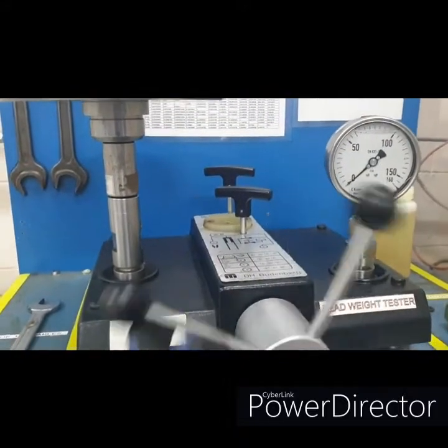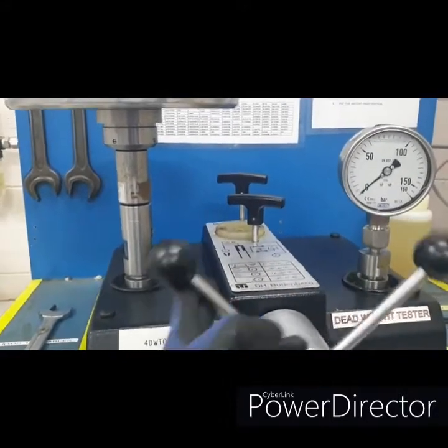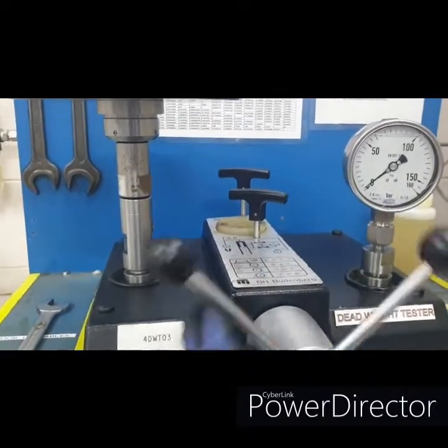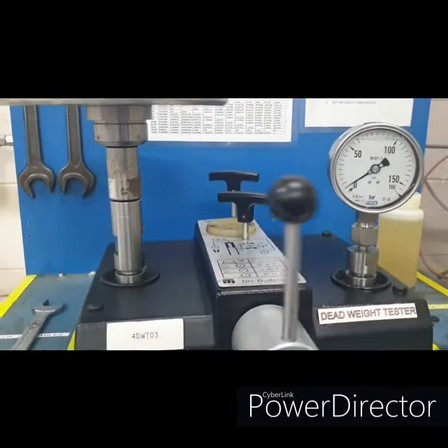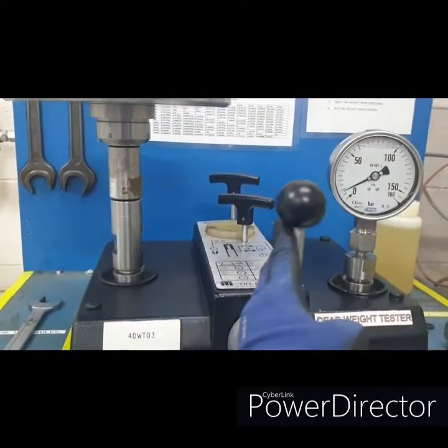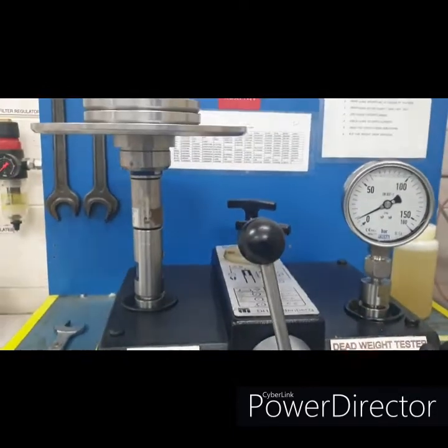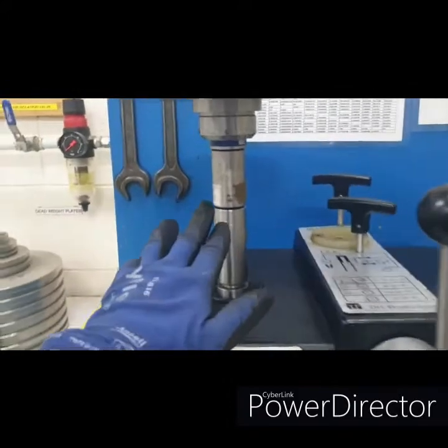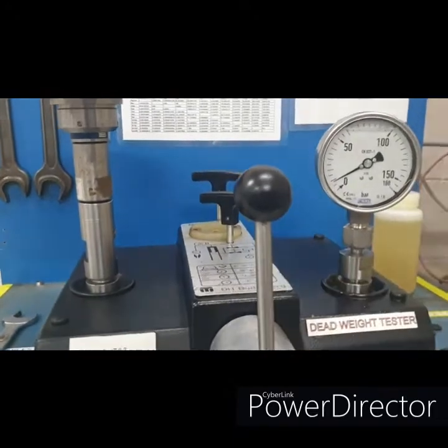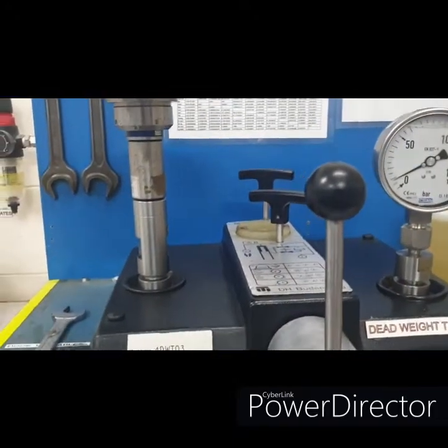So apply low pressure. So we're going to expect 10 and the weights will start to float. So start to float now. So as you can see that at this low pressure indicator, so it is around 10. So there is a little error in the pressure gauge. So that is a pointer error, I think so.